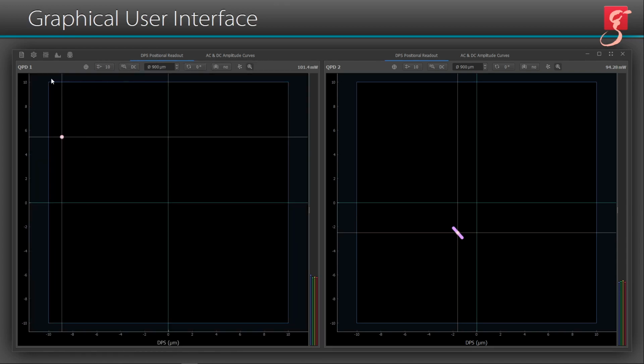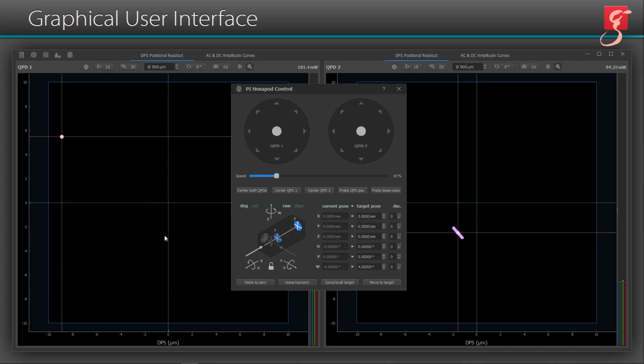And finally, up here we have 5 buttons which let the user export measurement data, edit basic application settings, create and load analog front-end calibration profiles including offset and gain corrections, and control the laser's amplitude modulation along with the signal's demodulation. And the last button gives you access to the automation I mentioned before, as this controls the Hexapod underneath the QPD. This part is still heavily under development, and only half of the functionality has been implemented so far. Here you can configure the QPD's 2 possible input ports.